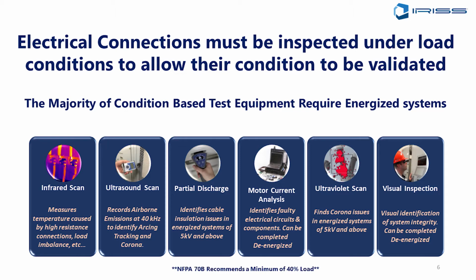Ultraviolet is used also for detection specifically of corona, a type of partial discharge. It will also give off not just ultrasound, but ultraviolet light. So we can use a UV camera, which is at the opposite end of the spectrum from infrared, right? We're at the high end of the spectrum, whereas infrared is the low end of the spectrum of light. And we are looking for the optical visualization of corona with a UV camera. So it's something used by utilities to exactly pinpoint where a corona event might be happening, and by any large industrial customers that have their own medium voltage and high voltage switchgear. They may also use UV detection as a technique.